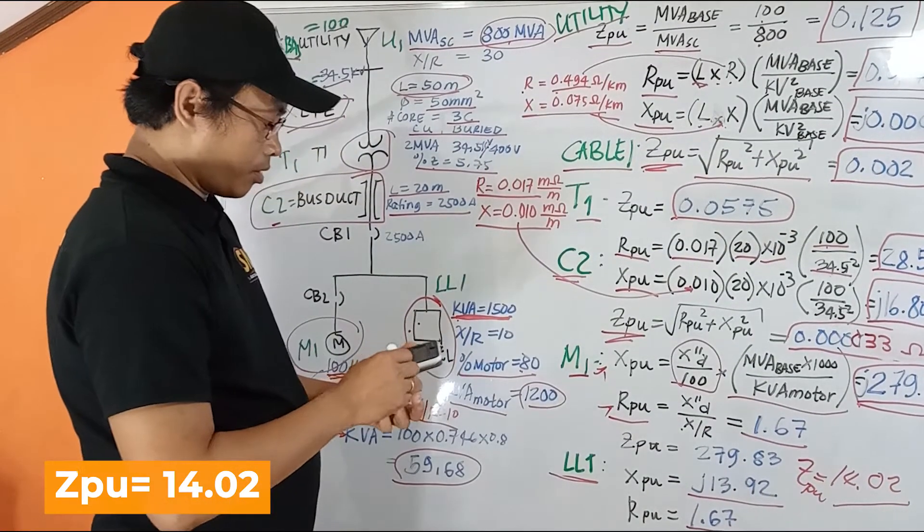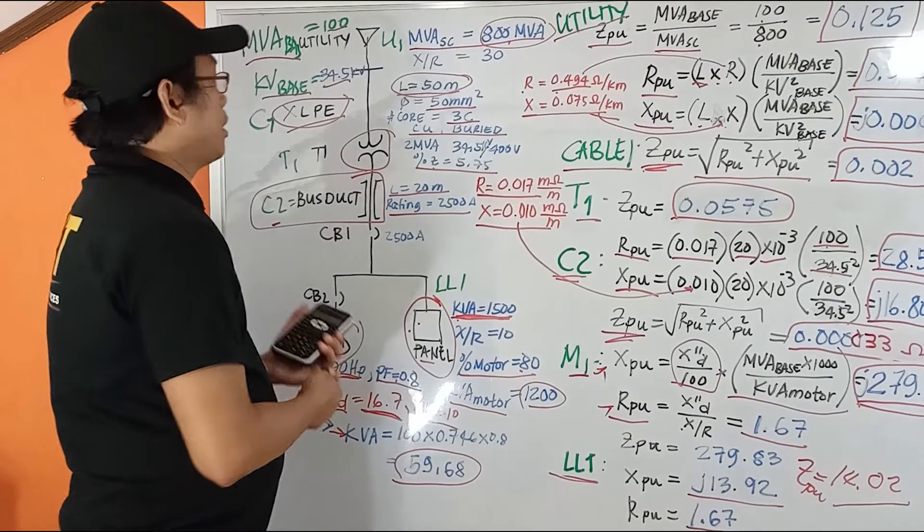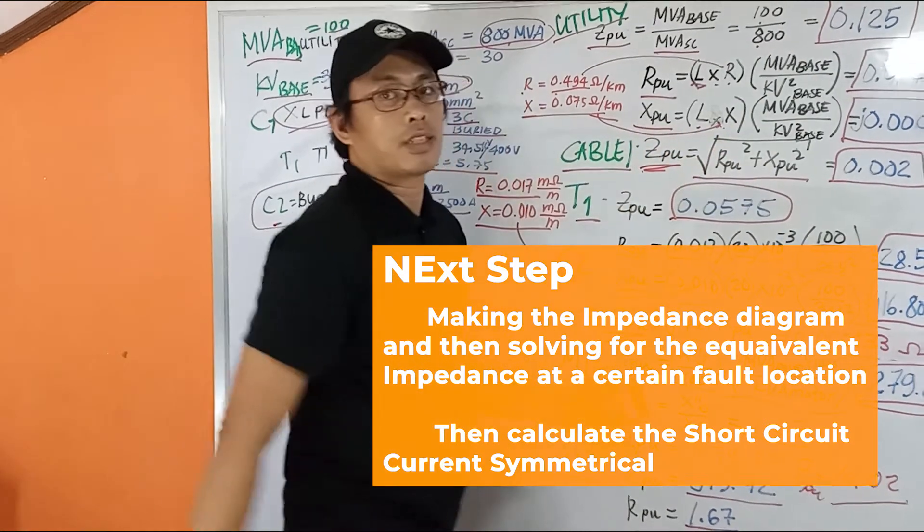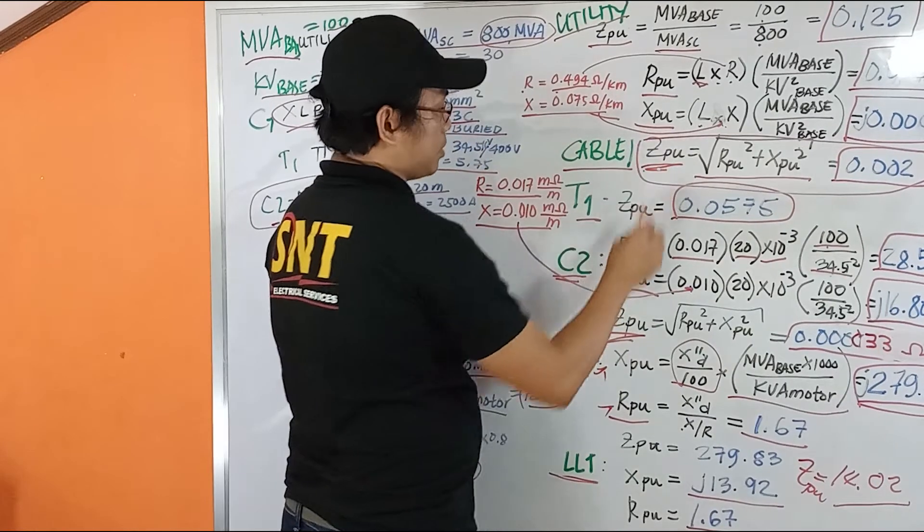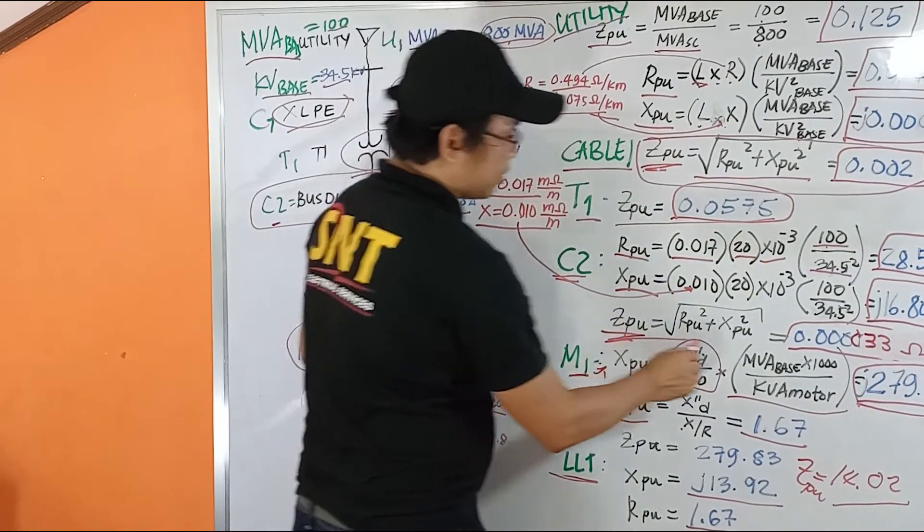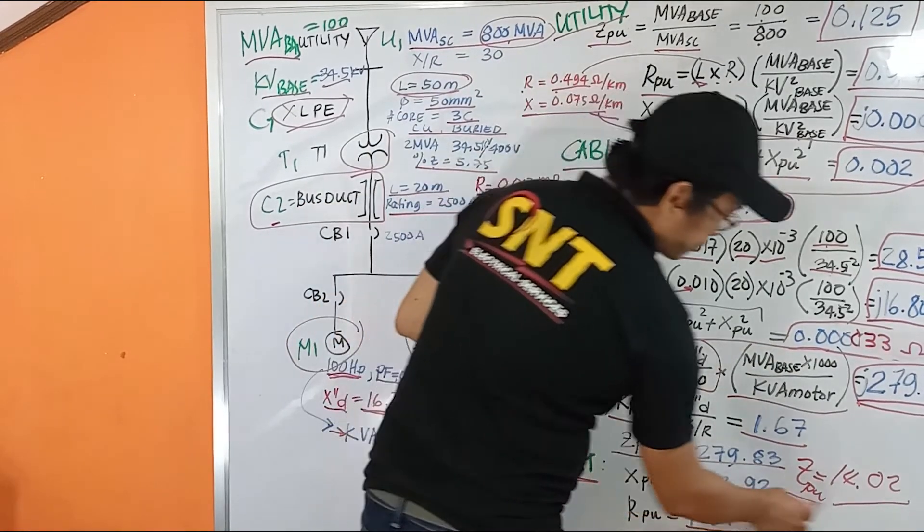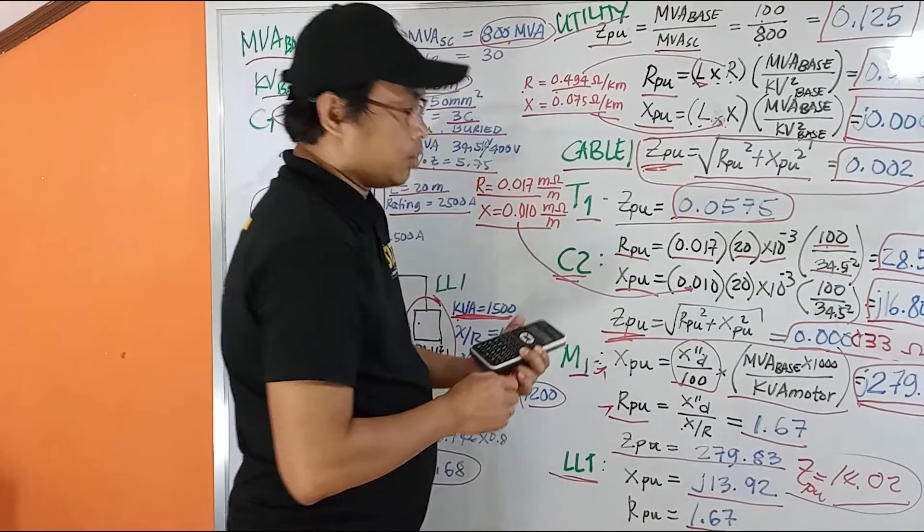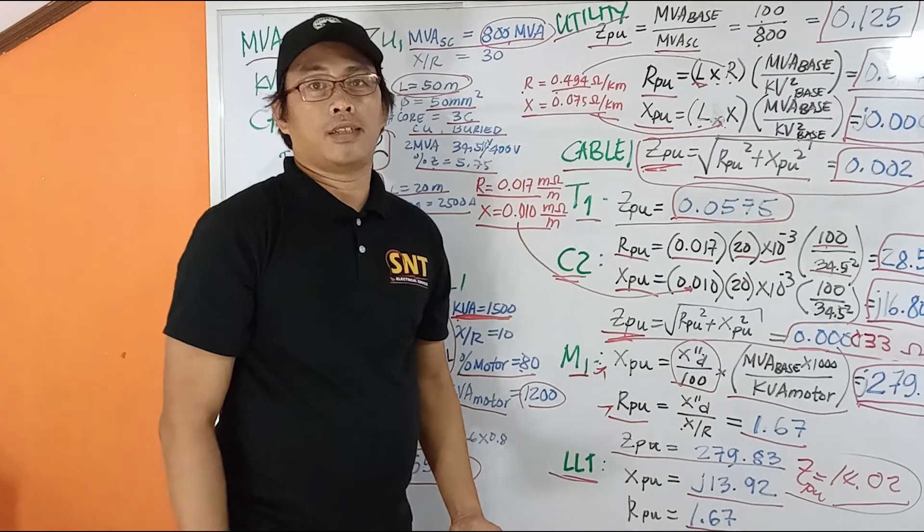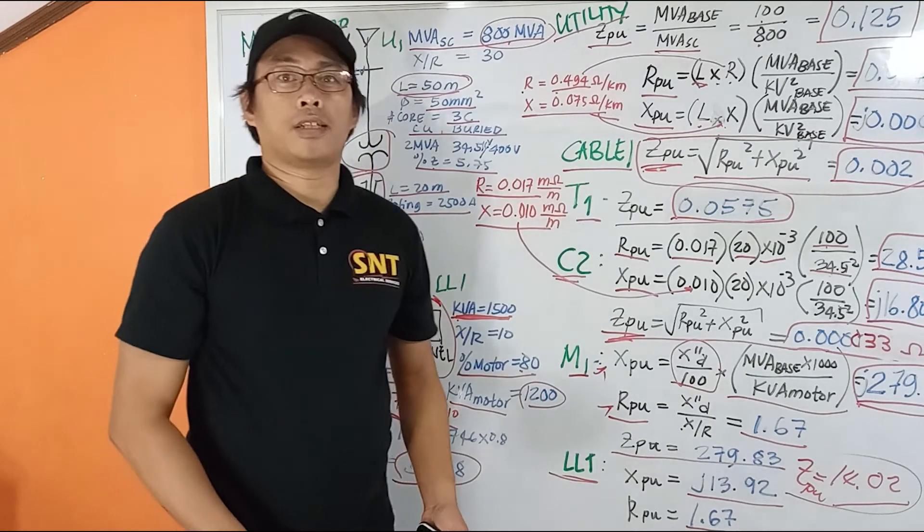So what does this mean all about? After getting all the data or the information on our single line diagram, then we use this formula and substitute it. Then we get all our per unit impedance. We need per unit impedance here, here, and our per unit here. Then we do the impedance diagram after getting all the data, or calculated values.